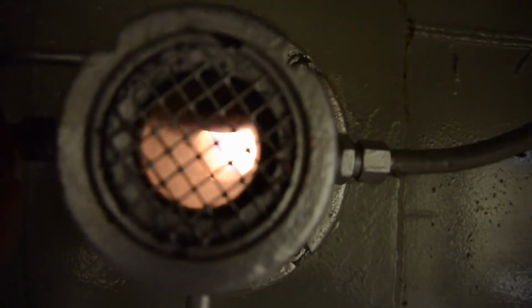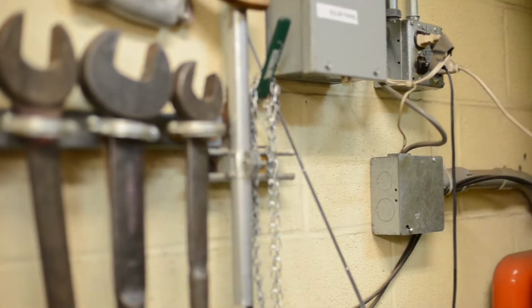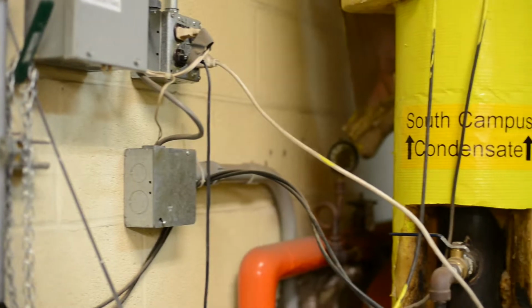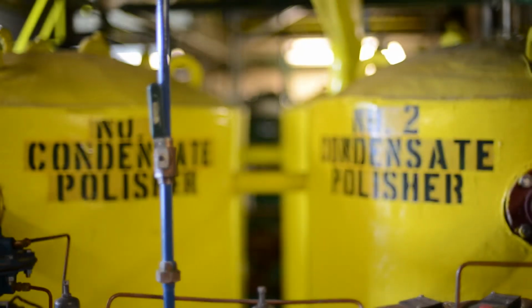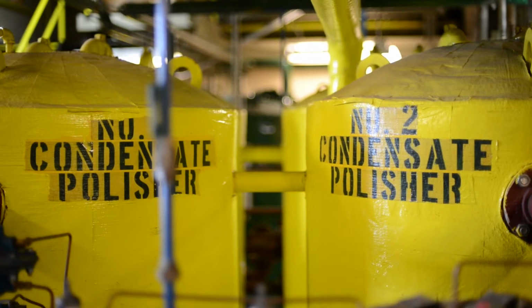In a central heating system, the percentage of condensate that is returned to the boilers for reuse is a good gauge of a plant's overall efficiency. Experts normally accept around 60% condensate return as a reasonable number. You're heating water up and you're making steam, and that steam goes out to the building and does its work. And when it turns back to condensate, which is a water form, it's still hot. It's not 50 degrees, it's like 160, 170 degrees. So every pound of condensate you get back, you have all those BTUs stored in there, as well as it's already treated and it's got chemicals in it.